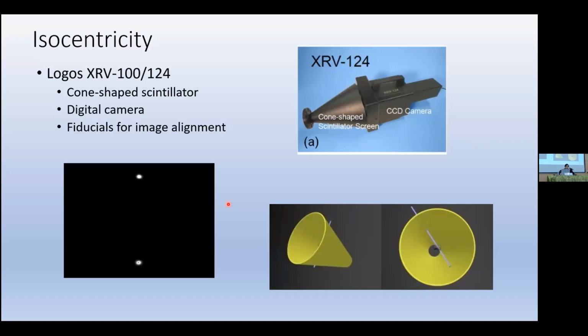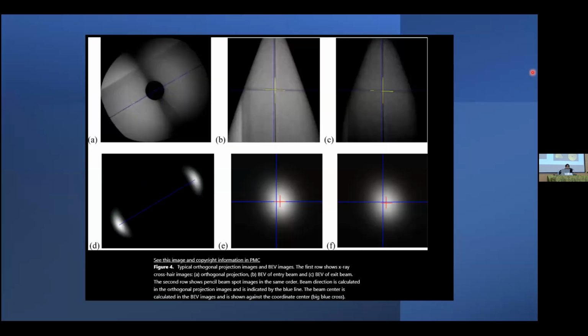Other things that you're going to be using a detector for, this is the Logos system. So remember, now we have a beam, one spot going down the central axis, and you want to check your gantry rotation. You want to check mechanical isocenter versus radiation isocenter, like in photons where you're doing this Winston-Lutz type of check. Similar, but you have a different radiation mechanism and you have a single spot. So there are different ways you could check that. This is one method to check that. Here are some measurement results. So then you could check your radiation and mechanical isocenter as the gantry is rotating, and you could do this also with your patient positioner as it moves.